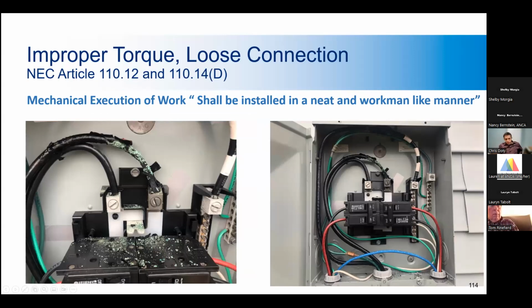Here we see an interesting situation. These are two pictures of the same panel. You can see the left lug looks normal, but the right lug is discolored, and obviously the insulation is in terrible shape. What happened here is the right lug was not tightened down correctly, and the wire was loose in the lug, so it didn't have a good connection. And the temperature of the wire went back and forth, and it burned off the insulation. Then since it's outside, condensate got in there and caused the copper to corrode and flake off. The only way to fix this was a complete replacement. So we don't know if the copper shards fell down into the breakers, causing them to fail. So the only way to fix it was the contractor had to come and replace it all. So that lug should have been torqued down to the value specified by the manufacturer.